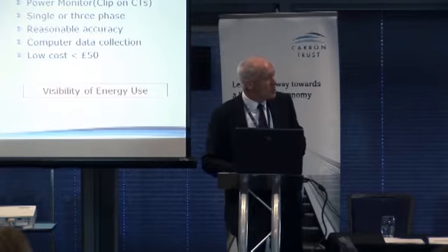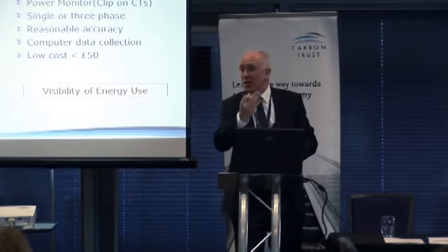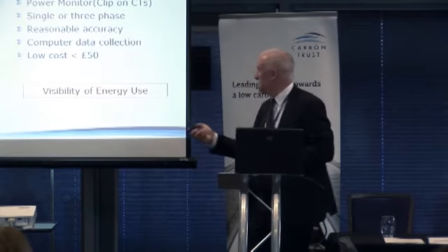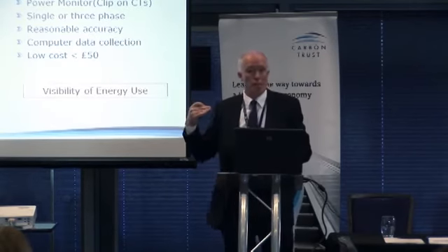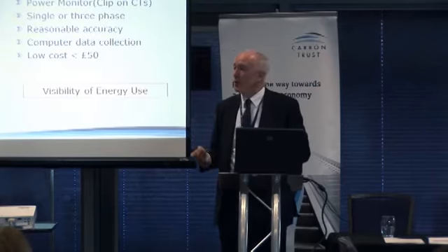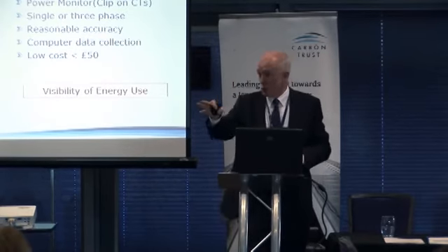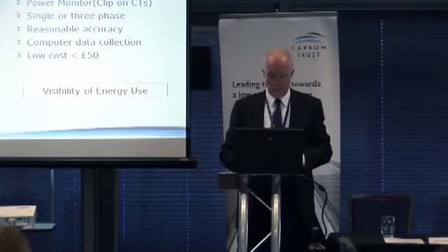And if someone says, well, should we switch the lights off in here because the sun's out? No, it's not worth doing. You can switch the lights off, and within 10 seconds this will start to respond and drop down by the load. And you can say, yes, it is worth doing. Look, it's reduced that load. It's very simple, very pragmatic, and really useful in schools as well. I've used them a lot in schools and they worked very well.